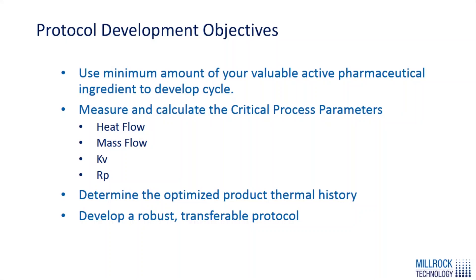A couple of objectives when developing a new freeze drying cycle or optimizing an existing one is that we want to do this using a minimum amount of valuable active pharmaceutical ingredient or protein product. Throughout this cycle, we need to measure and calculate our critical process parameters, such as heat and mass flow, our Kv, vial heat transfer coefficient, and our product cake resistance, Rp.